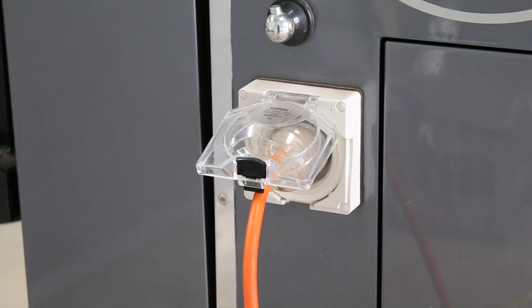But we've also got a 240 volt input on the outside right there, and once you connect that to shore power, generator, or the grid, whatever you've got available, the inverter will detect the outside 240 volt connection. Once it's stable and has been tested for about 10-20 seconds, it will push the 240 volt from the outside through the inverter, through the built-in transfer switch, through the RCD to protect all the outlets, and then to the outlets, and you're running on external power.